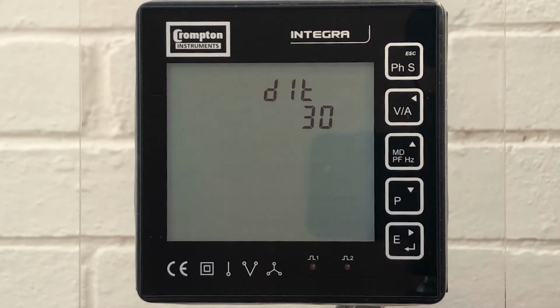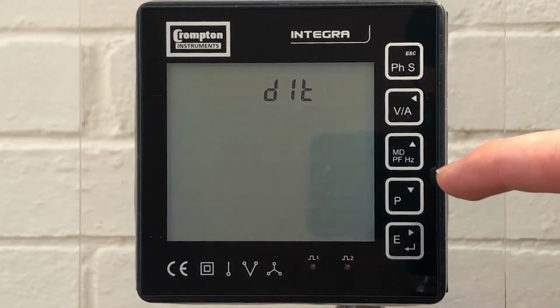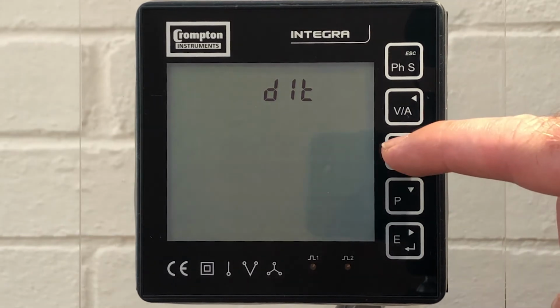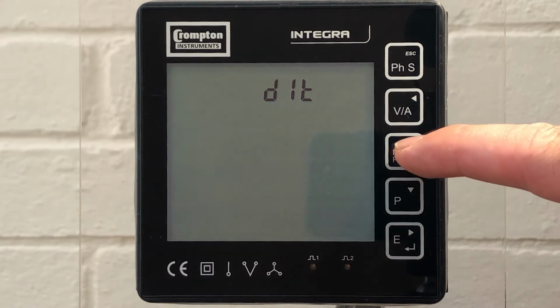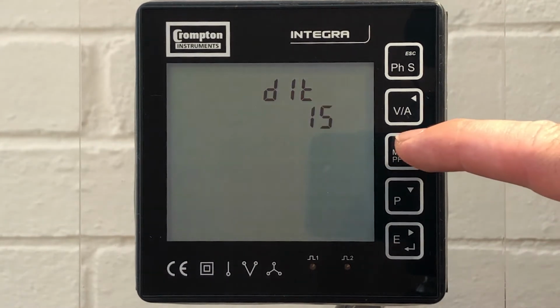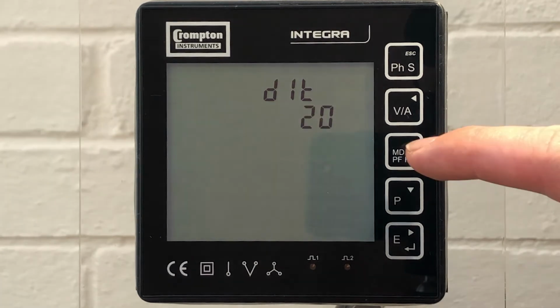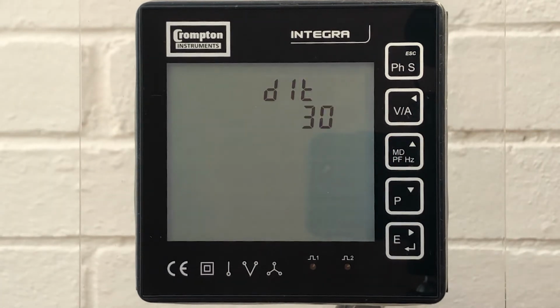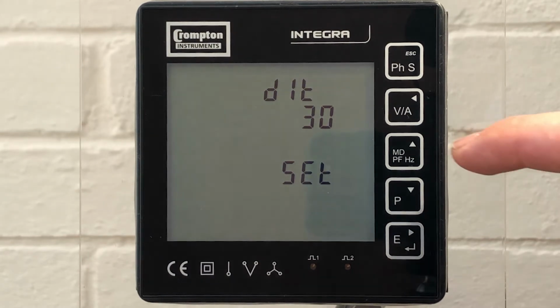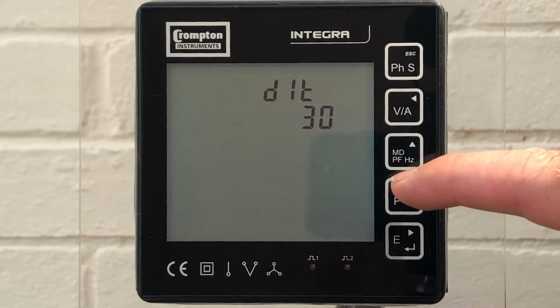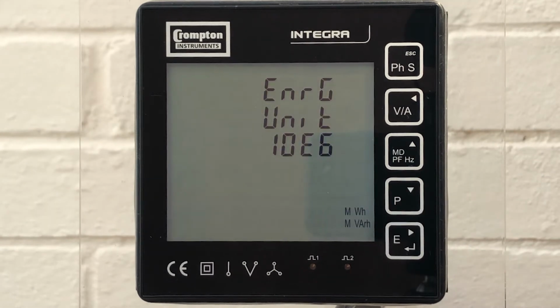And arrow down to our next settable feature, which is demand integration time. This sets the period in minutes in which the current and power readings are integrated for maximum demand measurement. The available options are 8, 15, 20, 30 and 60 minutes. In this example, we're going to set our demand integration time at 30. Having set that, press the VA button to move to the next selection, which is the energy units.